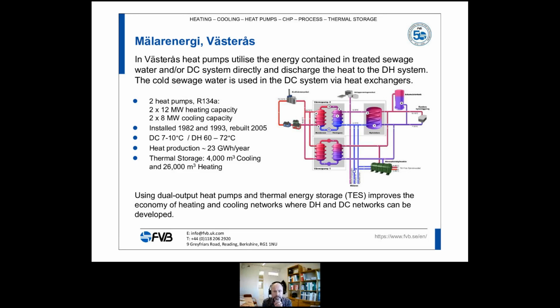We have a great example of that as well. And that's actually where I'm sitting right now here in Västerås, where we have two large heat pumps, 12 megawatt each. One is directly connected to the district cooling system to improve efficiency, and the other one is connected to the sewage water system. So you can run that pump independently of the district cooling system. However, you can also use it for the district cooling system, because when you cool down the sewage water, you run that through a heat exchanger and then to the district cooling system.